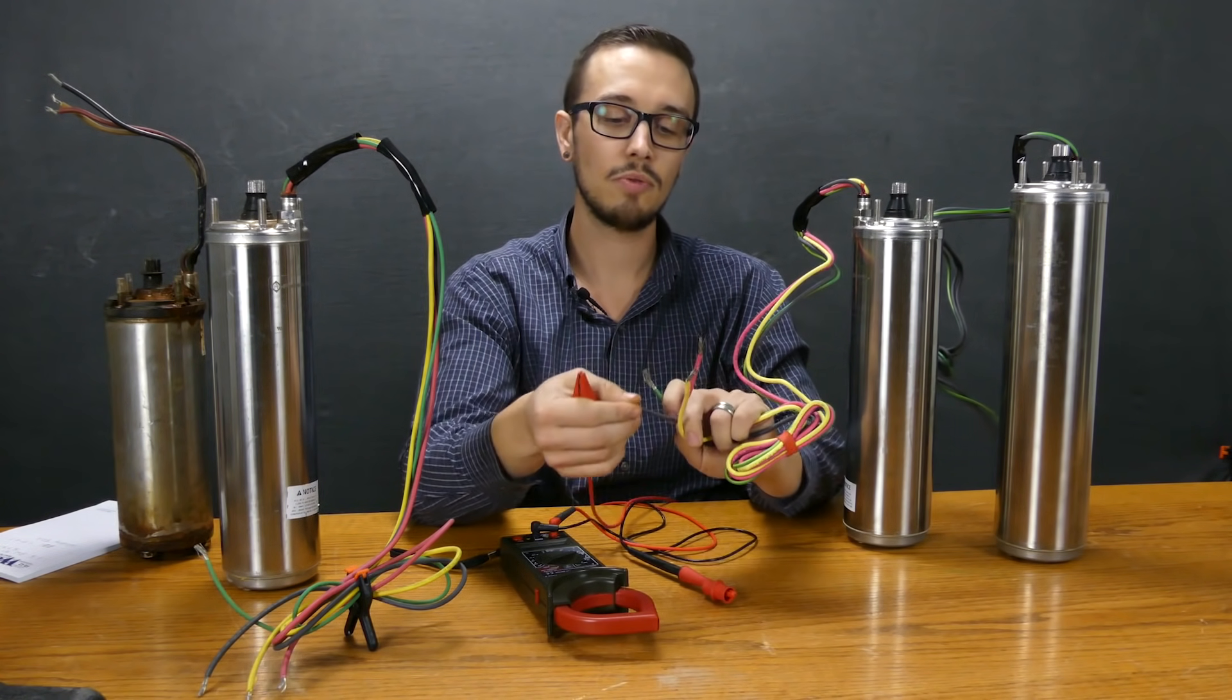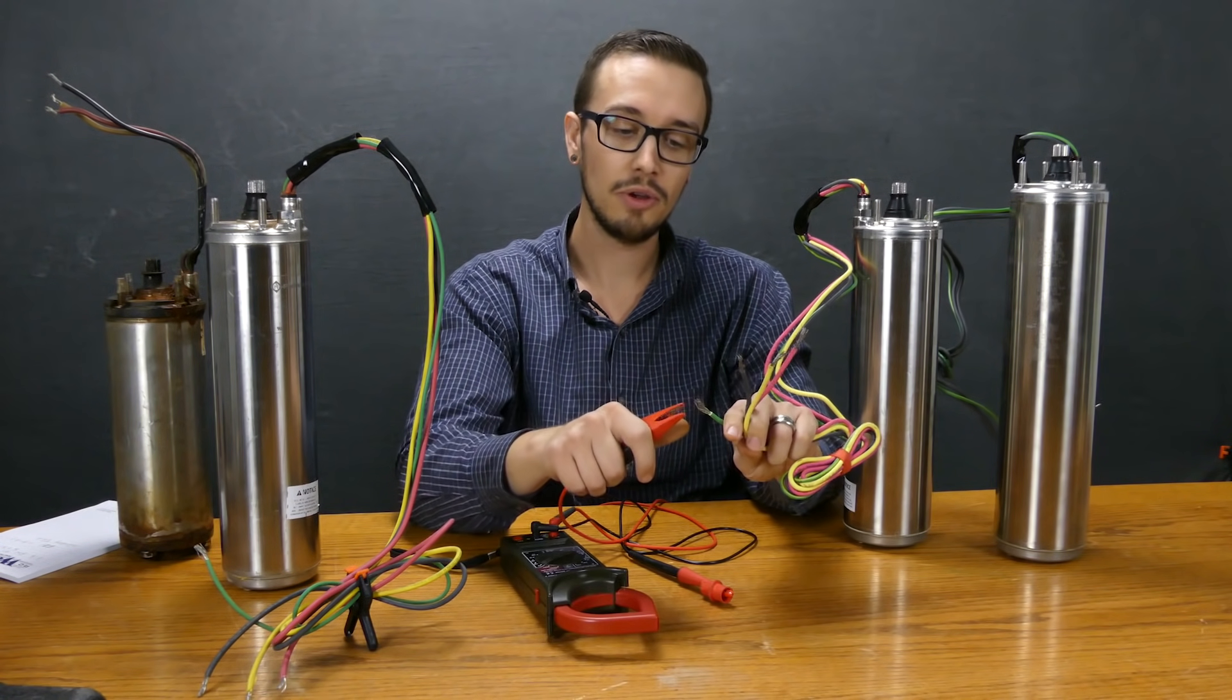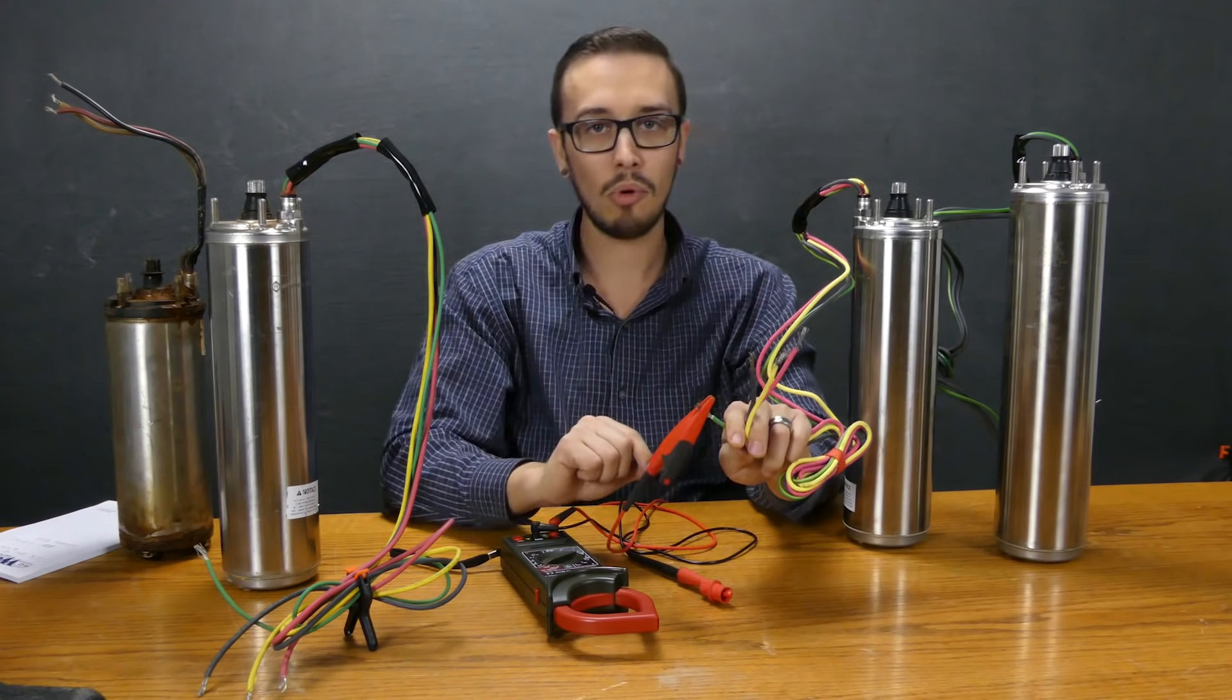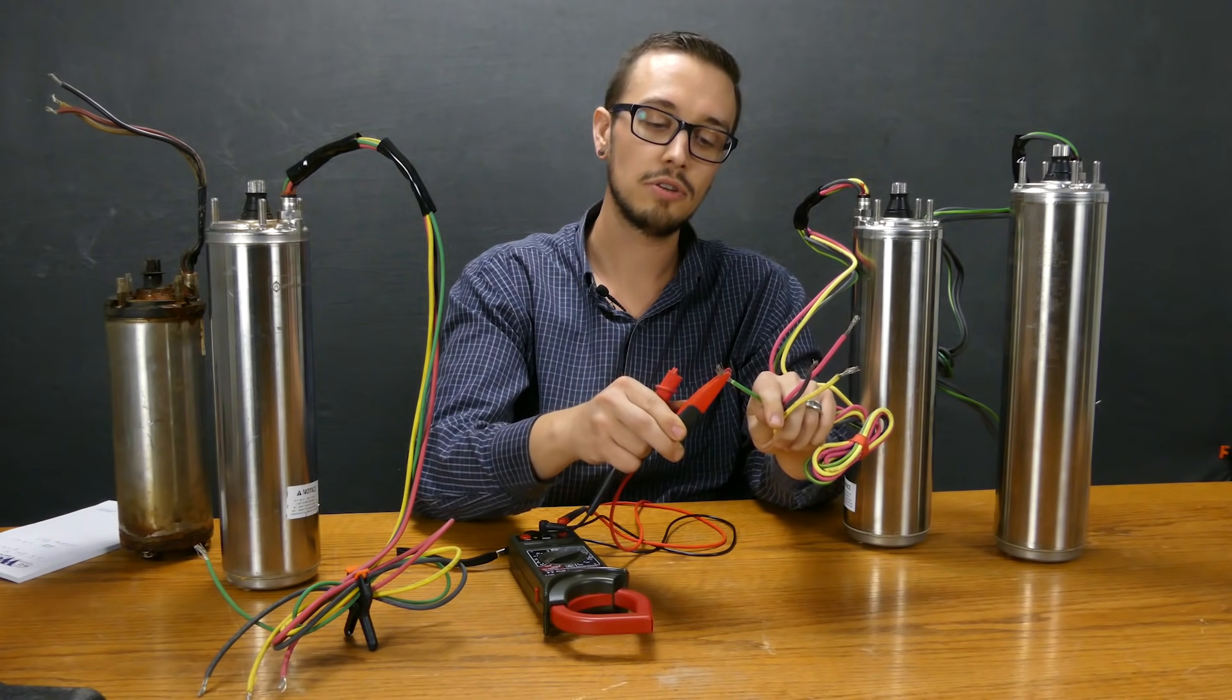The first test that we're going to perform is going to be the insulation resistance test where we actually test the resistance inside the motor's insulation. So what we want to do is in this case we want to hook one of our leads to ground.